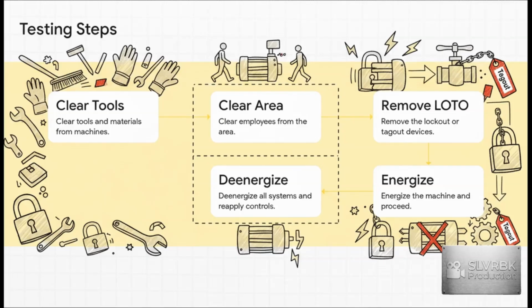Second, get all employees out of the danger zone. Make sure everyone is completely clear. Third, safely remove your locks and tags. Fourth, energize the equipment and run your test. And finally, step 5, before you do any more actual maintenance, you must immediately de-energize and reapply your LOTO controls. Like I said, it's a tight, strict cycle.